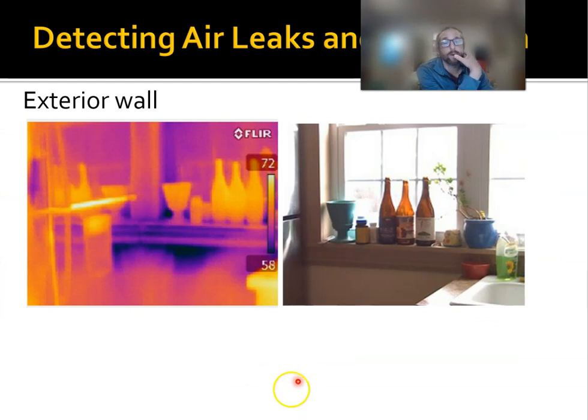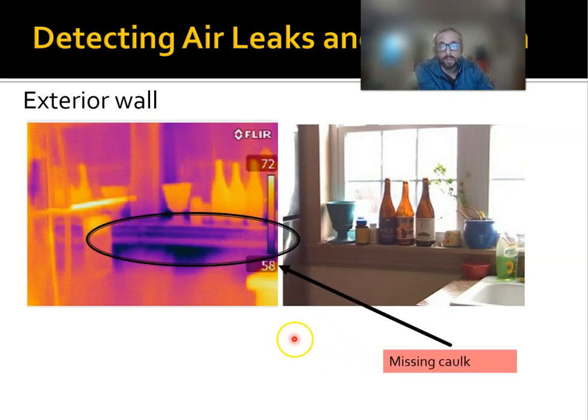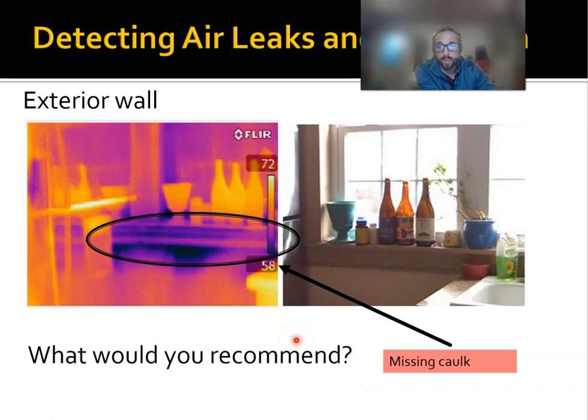So this is interesting. Same house, that two-story house I was just talking about. Regular old windows still, and running the blower door. But this is the IR image. So look what you see here. You see, again, more streaks. Okay. So there's some streaks coming out here. And so what's actually happening, believe it or not, is that there's caulk that is missing, right? So there's a bead of caulk that they should put down there. I mean, that's like a nickel's worth of material and 2 minutes of your time. And that would fix that problem.